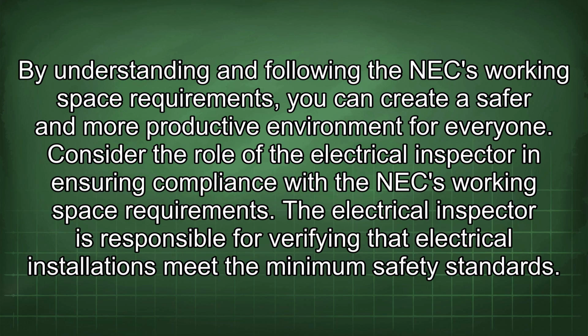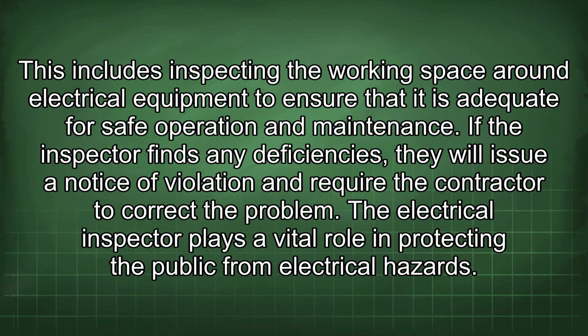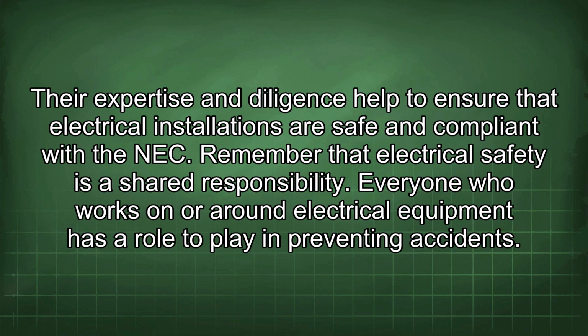Consider the role of the electrical inspector in ensuring compliance with the NEC working space requirements. The electrical inspector is responsible for verifying that electrical installations meet the minimum safety standards. This includes inspecting the working space around electrical equipment to ensure that it is adequate for safe operation and maintenance. If the inspector finds any deficiencies, they will issue a notice of violation and require the contractor to correct the problem. The electrical inspector plays a vital role in protecting the public from electrical hazards. Their expertise and diligence help to ensure that electrical installations are safe and compliant with the NEC.